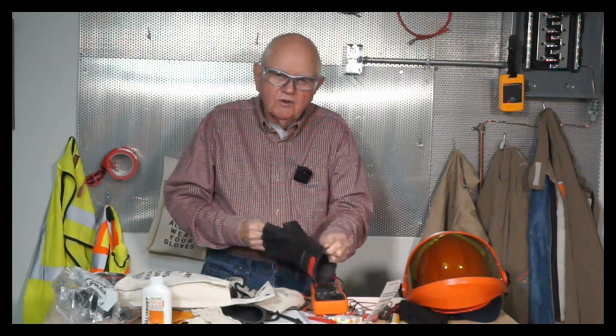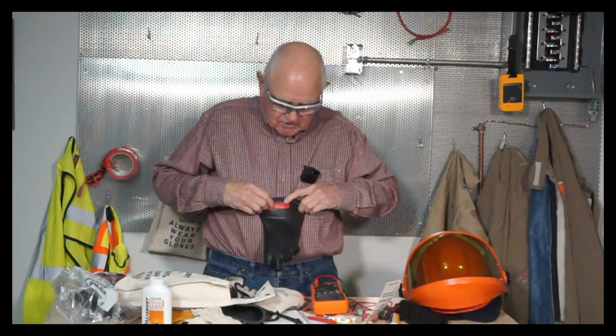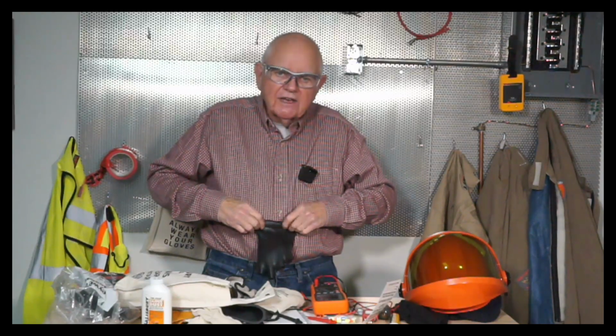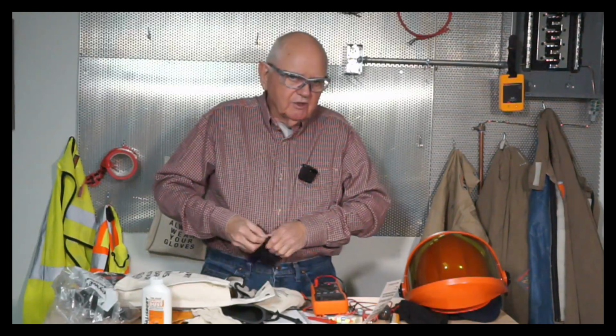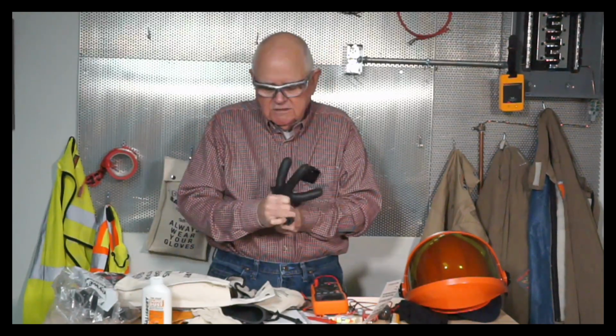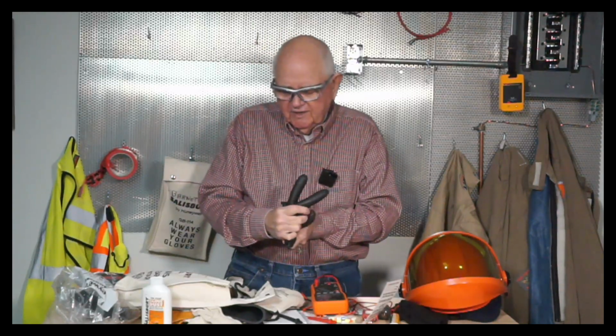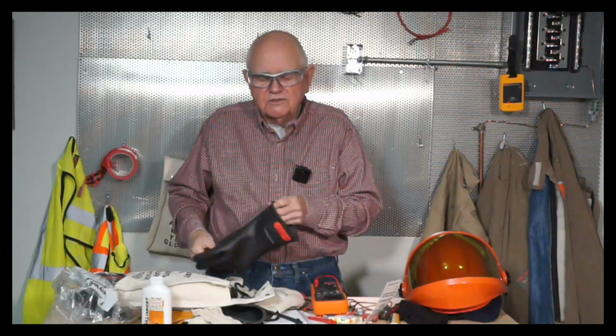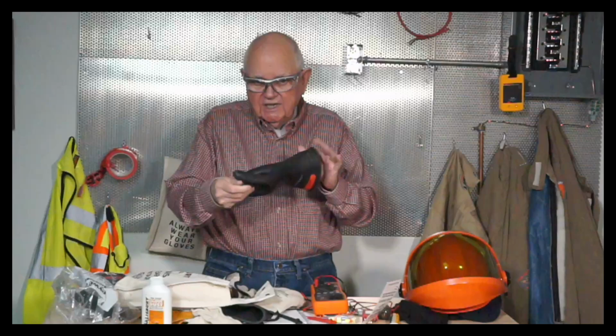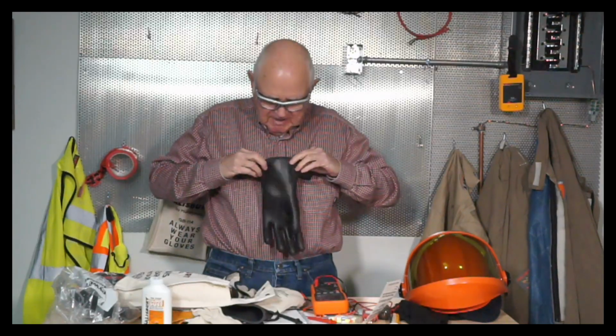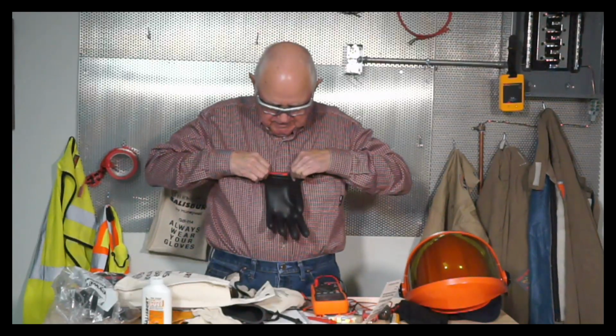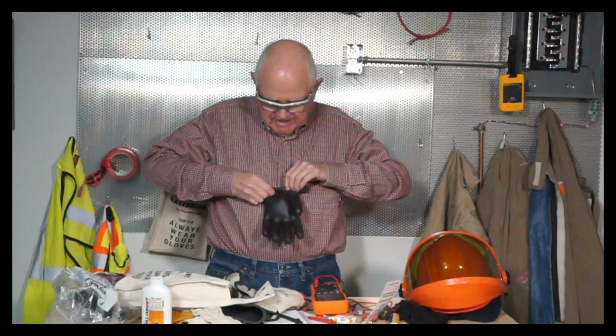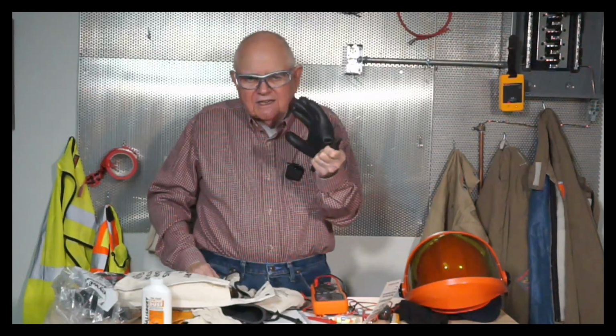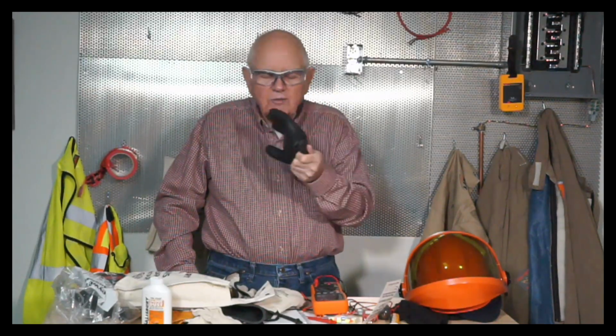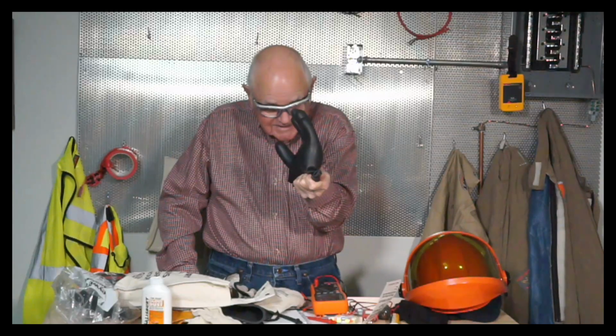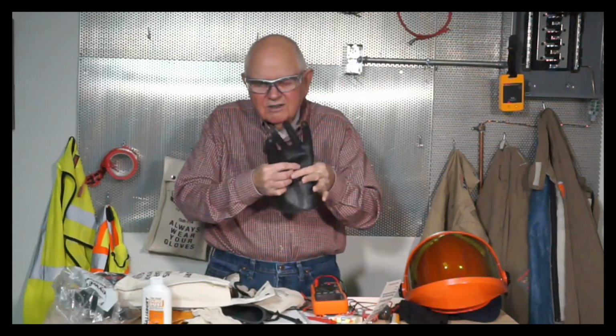I also have to do an air test on it. It's required. So whether I have a glove inflator, which is probably the best tool to have, and it's just a little portable inflator that I can set on my desk and use. But since I don't have one, I'm going to go ahead and trap some air on the inside, gently roll the glove up a little bit, get some air trapped. And if there's any air leaking, I'll hear it or feel it on my face. Looks like it's holding air.